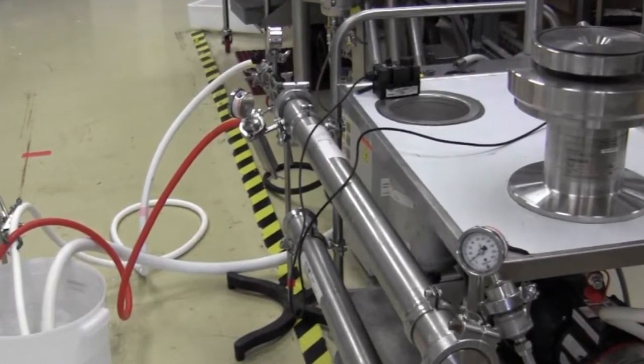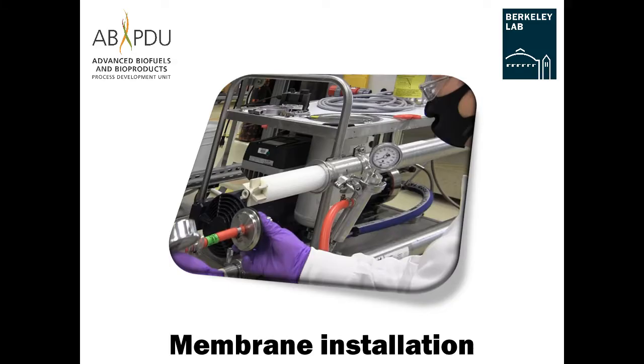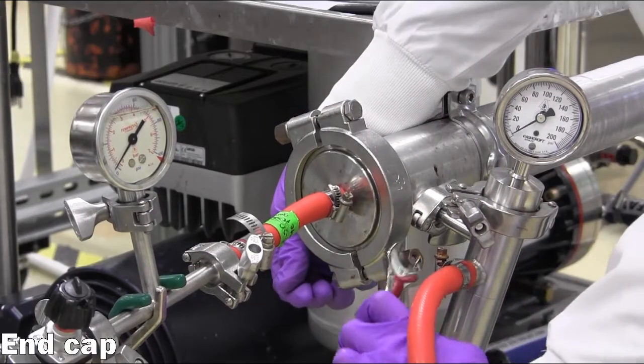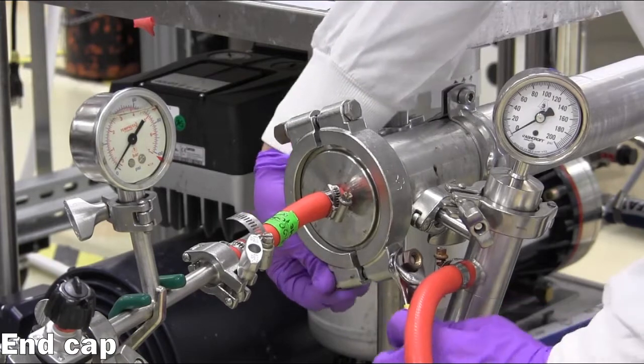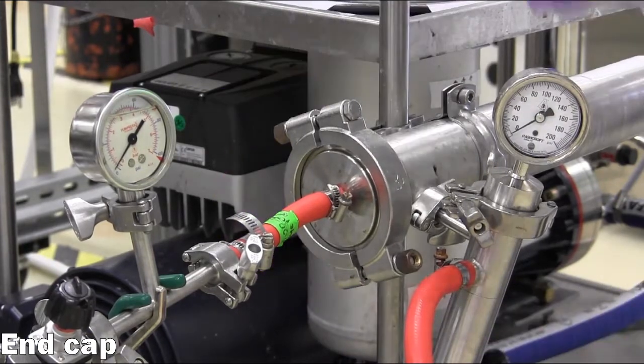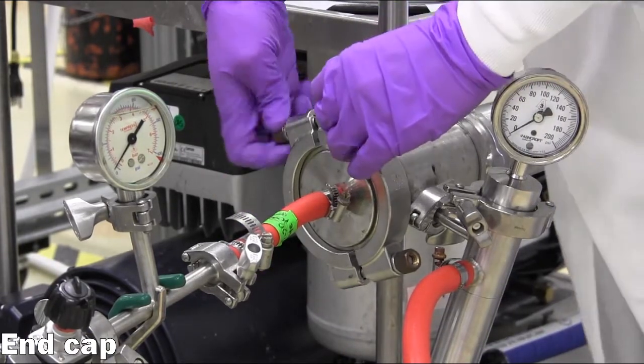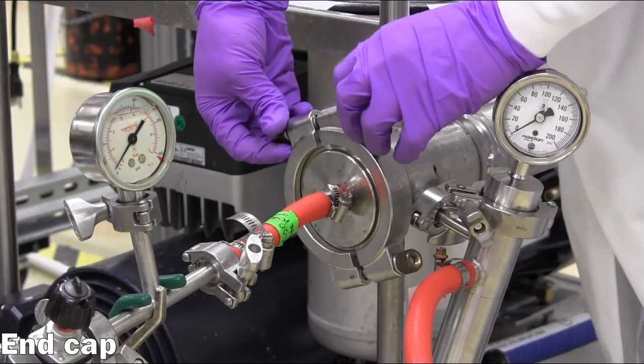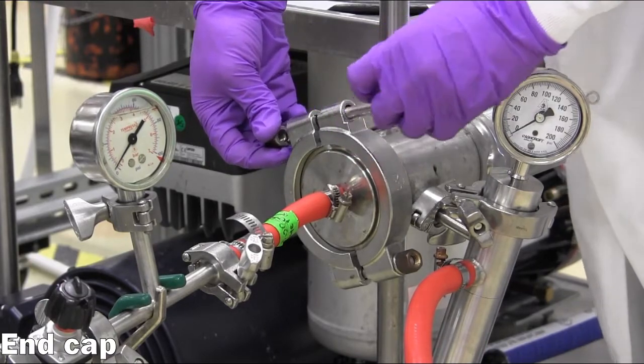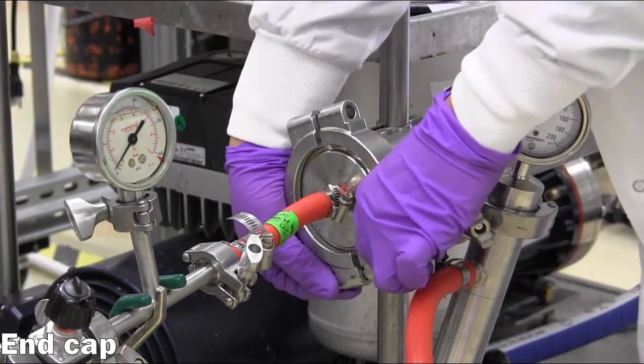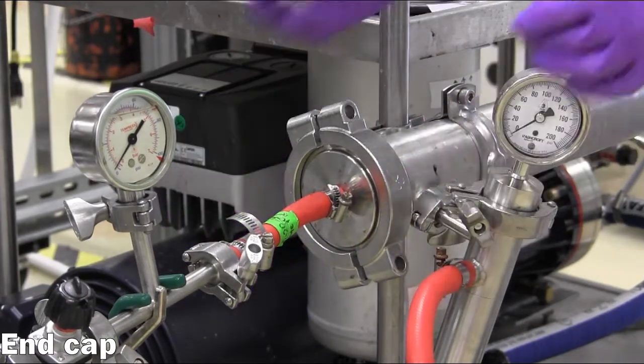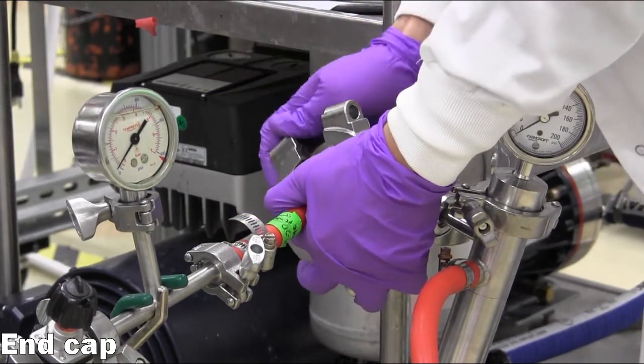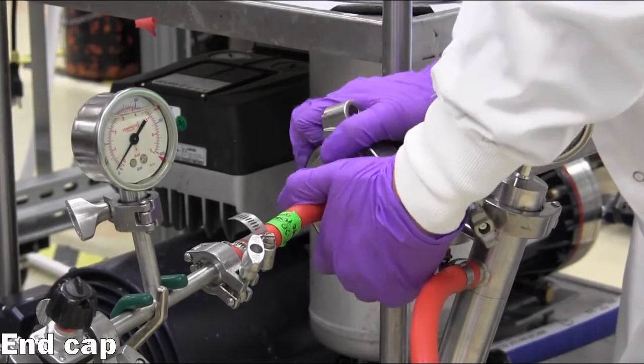Membrane installation. First, remove the end cap on the outlet side of the filter housing. This is done by unscrewing the two bolts that clamp the cap to the housing. A wrench may be necessary if these are tight. Then, the two sides of the clamp are removed and the end cap is separated from the housing.